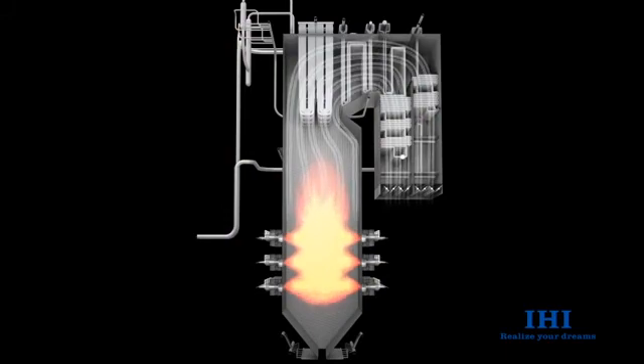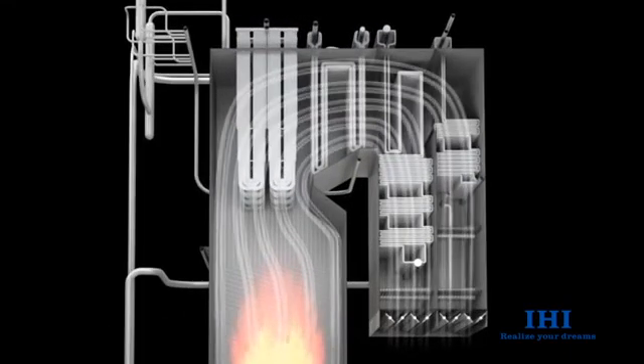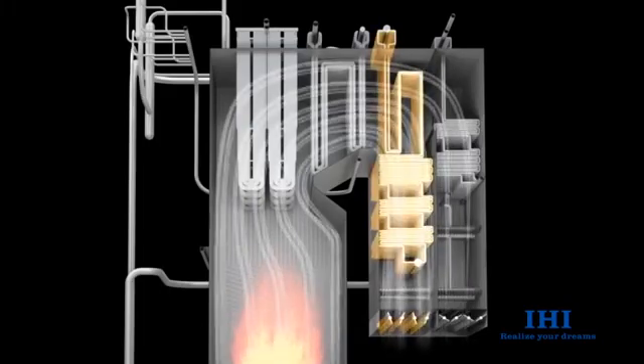To control the reheat steam temperature, the combustion gas flow rate in both paths can be controlled by the damper installed at the bottom of the heat recovery area. This is called the parallel path method, which increases efficiency compared to steam temperature control.